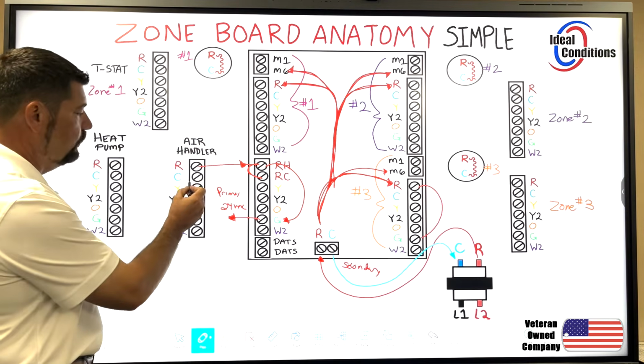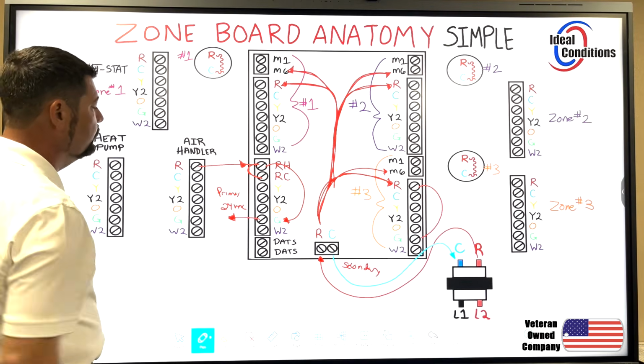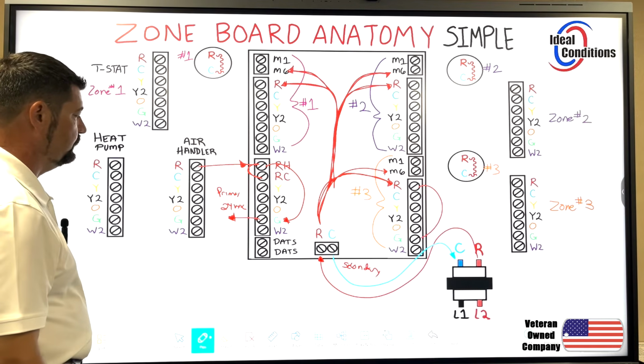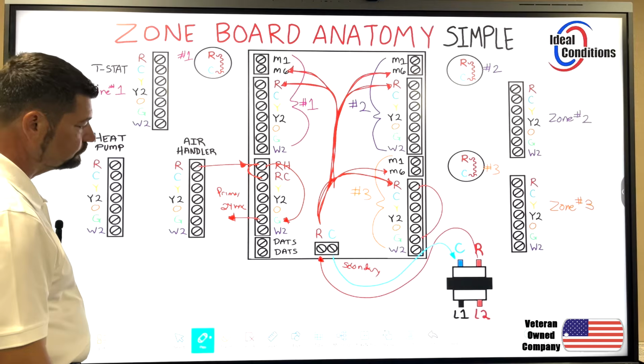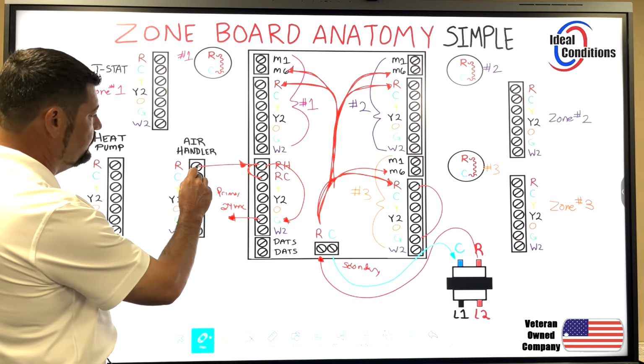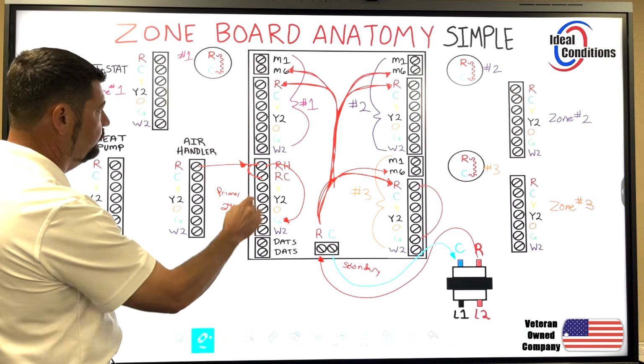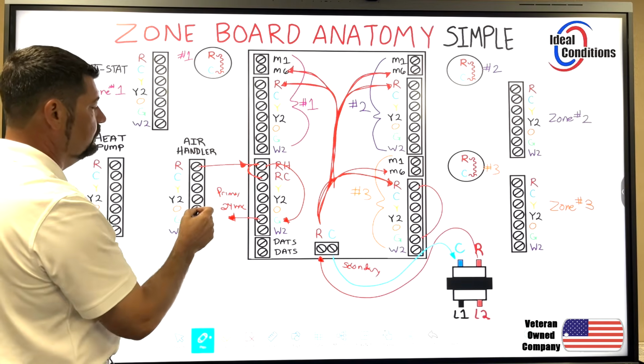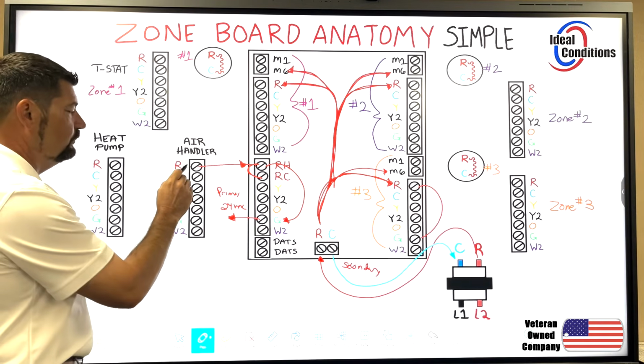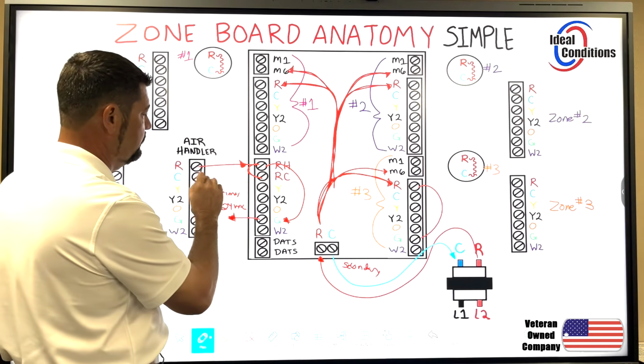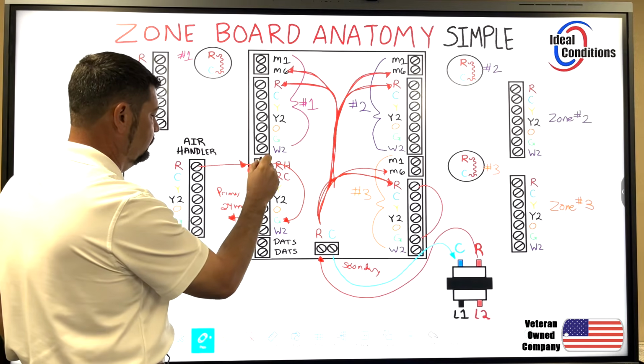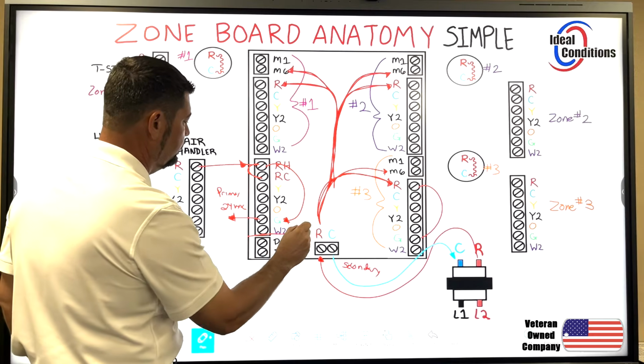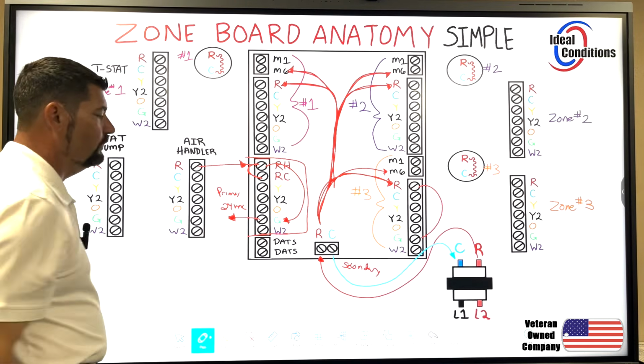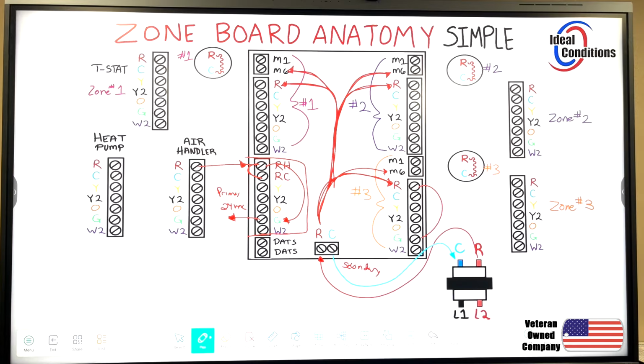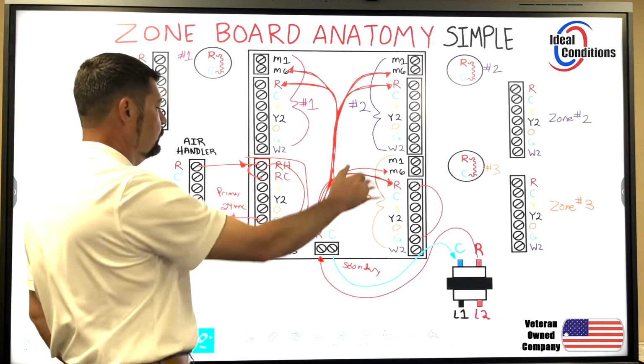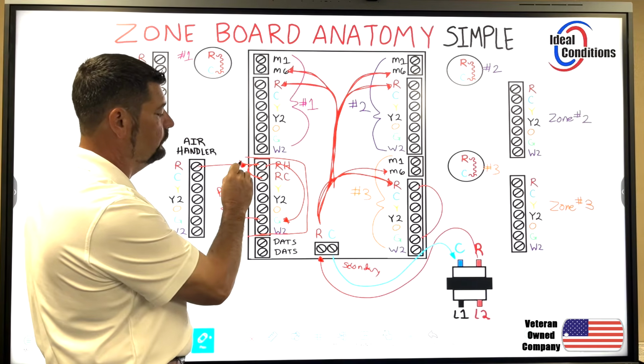Now you notice we don't have a common over here at all. We don't need it. You just don't need it. Okay? And so I have to have 24 volts to come here. And now it's the same thing as me having the 24 volts here. But what you have to understand is the 24 volt primary that's coming from the equipment, it's isolated. It's only in this area. It's nowhere else. It's only in that area. Nowhere else on that zone board where you read the 24 volts here.